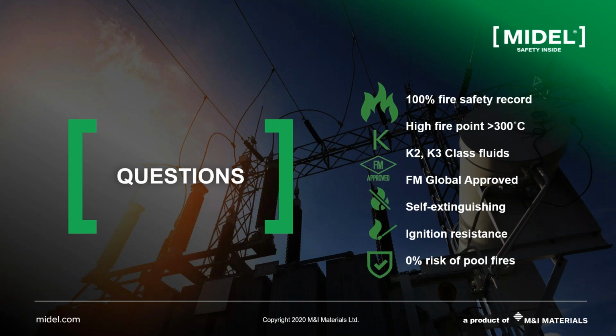Yes, I did. There was a slide where you indicated that you're typically looking at 66 kV and below for this sort of retrofitting action. Is that correct? Yes. So I think it's one aspect for this 33 kV or 66 kV. In the US, they use higher safety margins in the older designs, and so sometimes an older transformer can be retrofilled up to 66 kV. But in Europe, they adopted CAD design, and so they reduced the safety margins. And so in Europe, we are more conservative. We say up to 33 kV. But yeah, 66 kV is within the range. Yes.